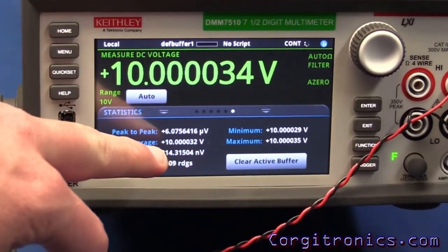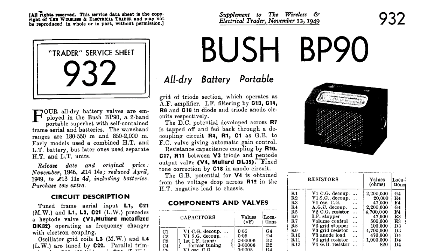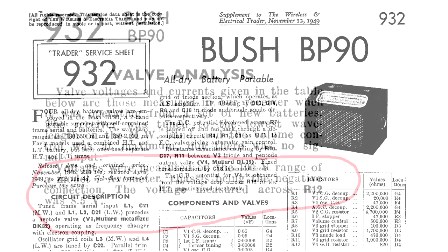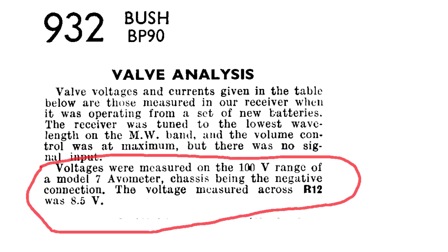I'm sure in the past some of you have looked at the service instructions for equipment like valve radios, and it's quite typical to find within the service instructions a description of the type of voltmeter that was used to take any measurements. So it's important to try to use the same type of meter as indicated in the service sheet, or you'll find your voltage measurements could be different to those indicated.